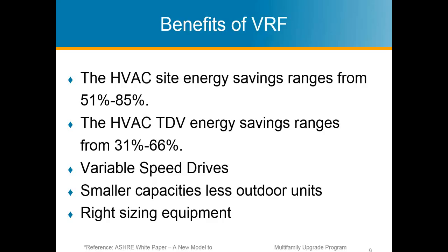So we're talking about right sizing the equipment. You know, you get penalized when you oversize equipment. So using these VRF systems with multiple indoor units paired up to one condensing unit really helps to right size the equipment as needed.